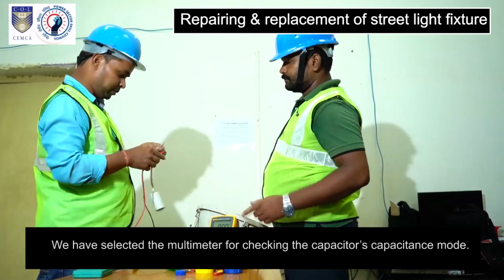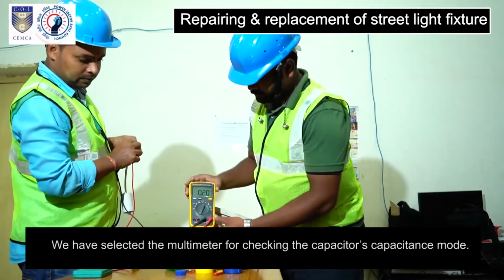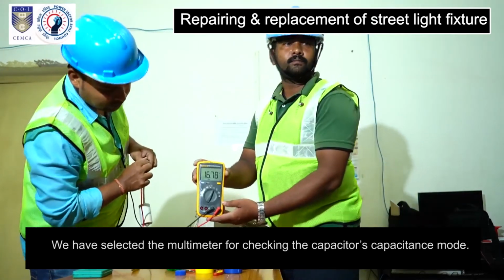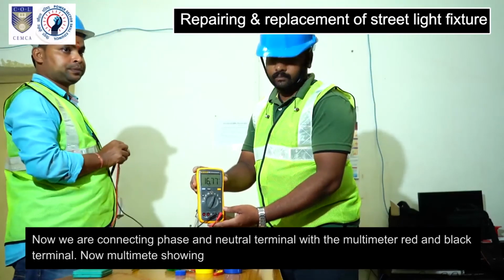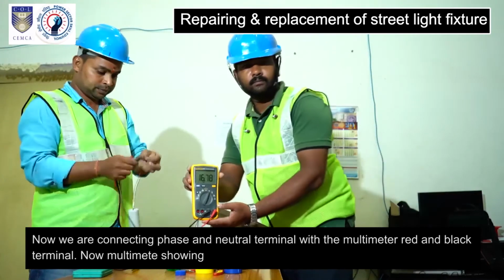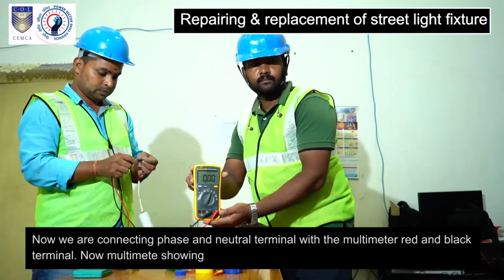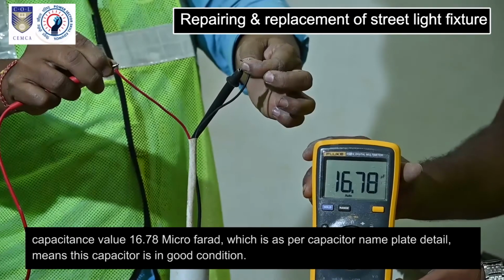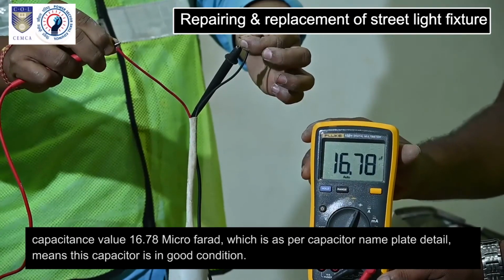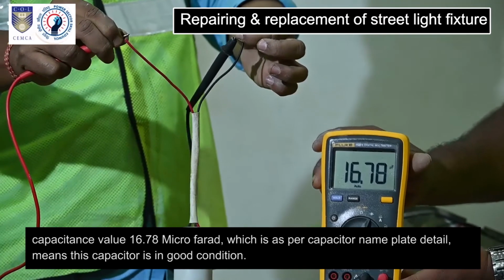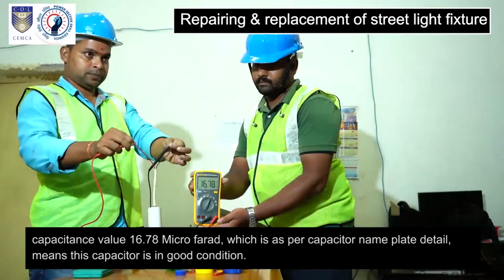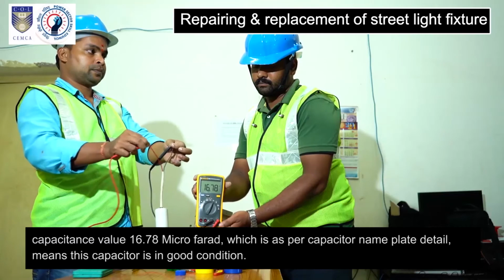We have selected the multimeter's capacitance mode for checking the capacitor. Now we are connecting the phase and neutral terminals with the multimeter red and black terminals. Now the multimeter is showing a capacitance value of 16.78 microfarad, which is as per the capacitor nameplate detail. This means this capacitor is in good condition.